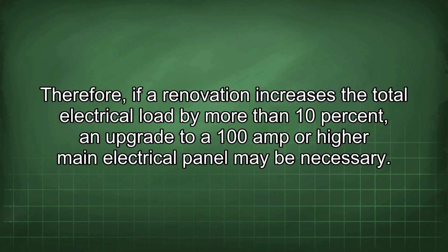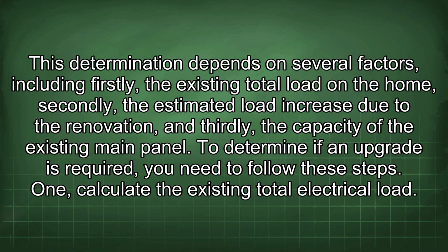Therefore, if a renovation increases the total electrical load by more than 10%, an upgrade to a 100 amp or higher main electrical panel may be necessary. This determination depends on several factors, including, firstly, the existing total load in the home, secondly, the estimated load increase due to the renovation, and thirdly, the capacity of the existing main panel. To determine if an upgrade is required, you need to follow these steps.